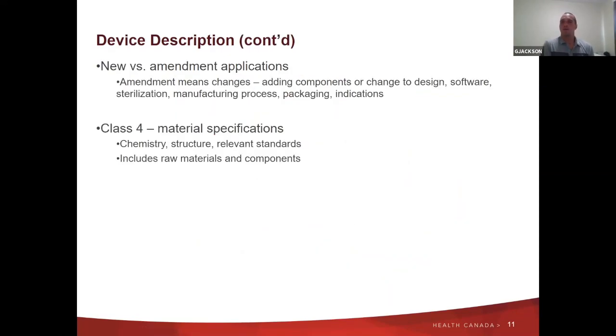Then we look at new versus amendment applications. An amendment is a device that's already licensed, but there are changes being made. We look at what we call significant changes, which require a full amendment application. Significant means something new in terms of safety and effectiveness that we haven't fully reviewed before. Like if they're changing the color of the cover on a device, that's not a significant change—it may just have a new device identifier, and they'd submit a brief application. But if they're adding a new instrument, changing the software, or want to use it for a new intended use, those are significant changes, and we take a full look at the safety and effectiveness of the device to make sure everything works as intended.